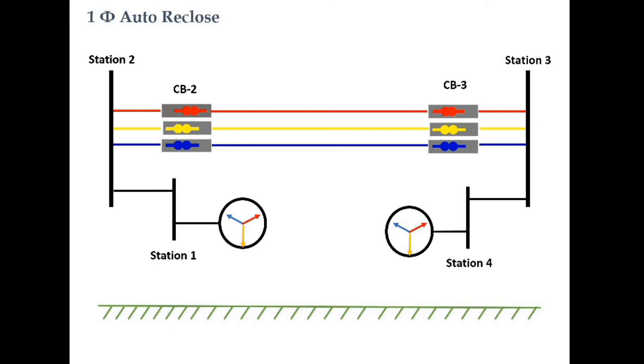There are basically two kinds of auto reclosure schemes used in EHV transmission lines: three-phase auto reclosure and single-phase auto reclosure. Transmission lines latched with circuit breakers having different mechanisms for their different phases can use single-phase auto reclosure, while circuit breakers with a single mechanism for all three phases use three-phase auto reclosure schemes. Let us start with single-phase auto reclosure.